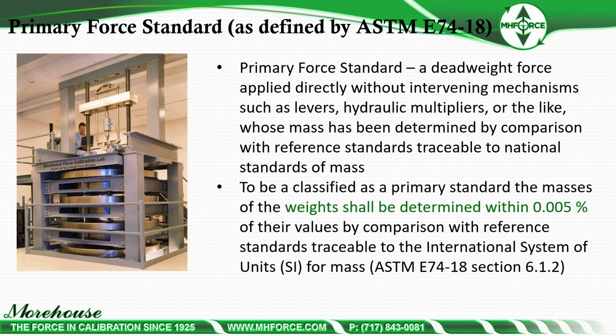It is a deadweight force applied directly without intervening mechanisms such as levers, hydraulic multipliers, or the like, whose mass has been determined by comparison with reference standards traceable to national standards of mass. To be classified as a primary standard, the weight shall be determined within 0.005%, that's 50 parts per million, of their values by comparison with reference standards traceable to the International System of Units, that's SI for mass. This is found in ASTM section E74 6.1.2.